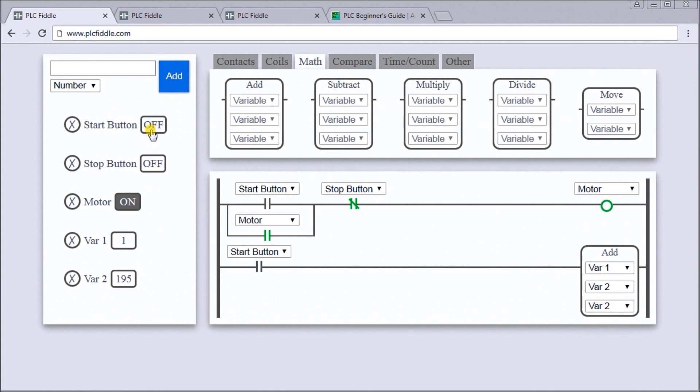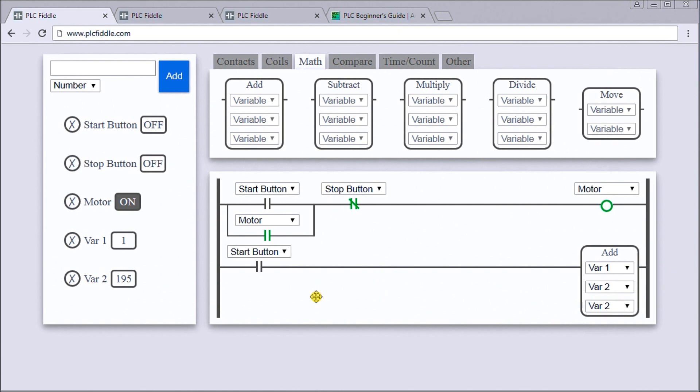We can turn it off now. In order to make sure that doesn't count on every single scan, we have to come up with a one-shot to control the add. The one-shot will only enable things to be added on the leading edge or from a signal from off to on.